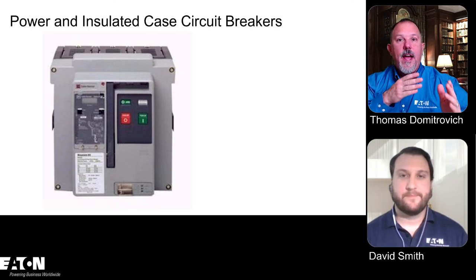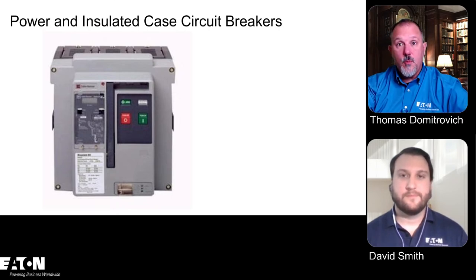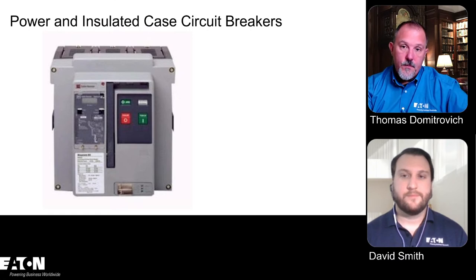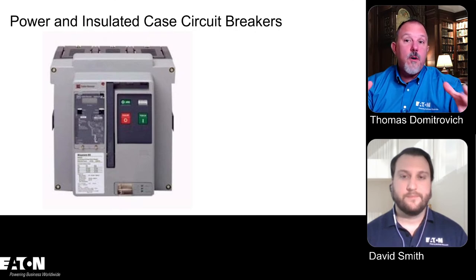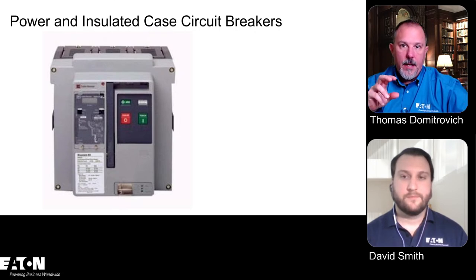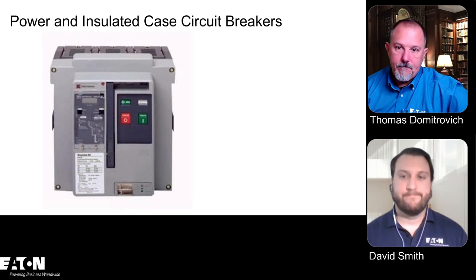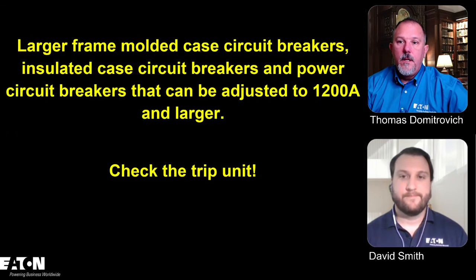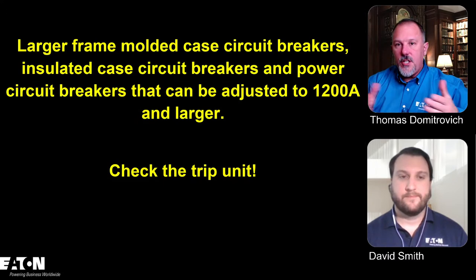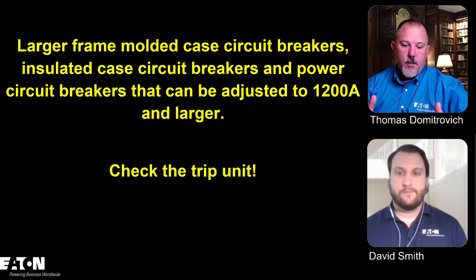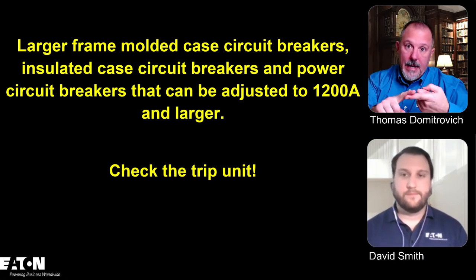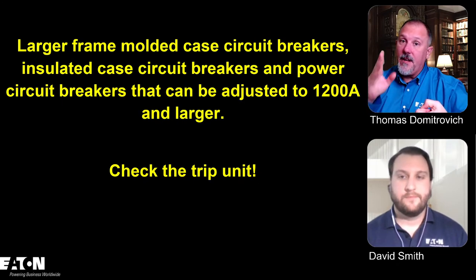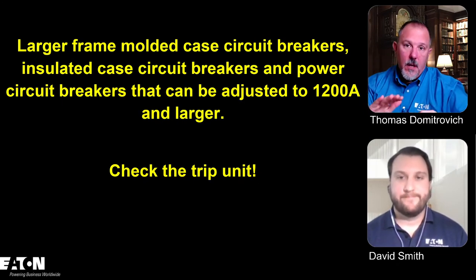And we don't have to have an arc reduction technology on a 1200 amp switch with an 800 amp fuse. Right. So same deal here. This could be a 1200 amp frame, but the plug rating might be something less. So that's the bottom line. What gets you into 240.87 is: can I adjust it? Forget about the rating, forget about 240.6 and whether or not you have the lock cover. Can it be adjusted to 1200 amps or above?